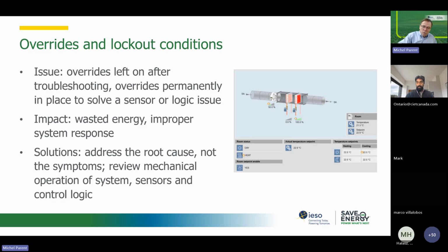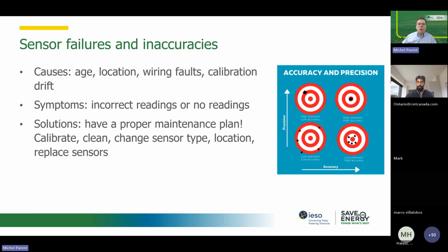So part, again, of your PM program for the BAS would be to always have a report of what points are in override, and then identify the root cause and when the override will be taken out, because overrides basically take away the value of your BAS. The more overrides, the less value the BAS that you paid for has. And we talked about the sensors. Sensor inaccuracies and sensor failures would be captured through the critical sensor calibration plan that you should have as part of your PM maintenance.